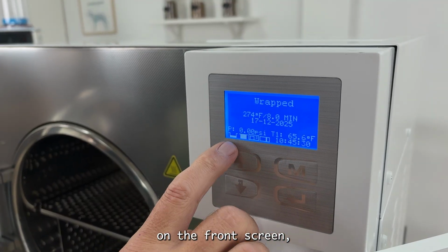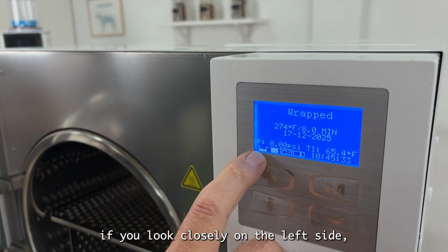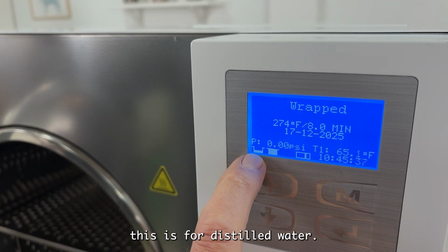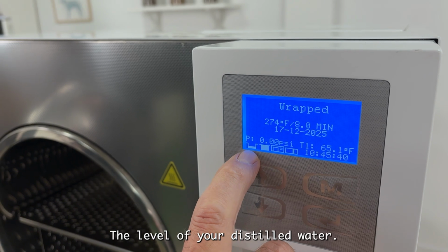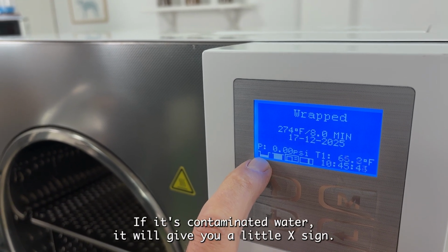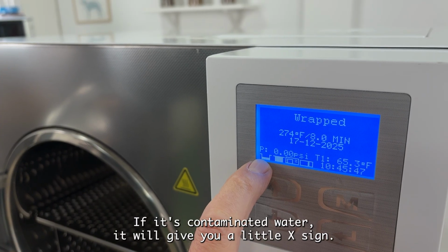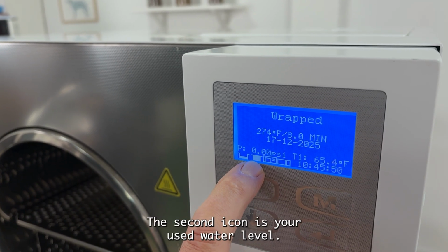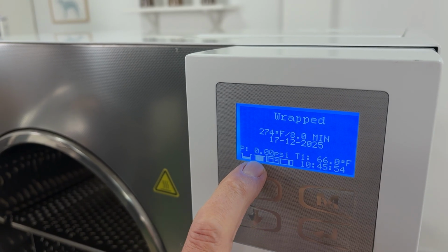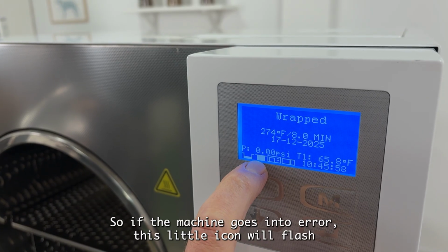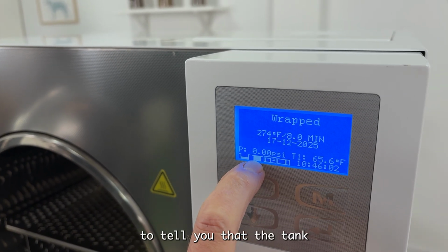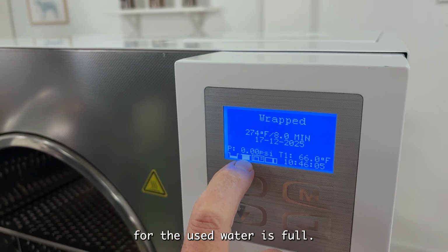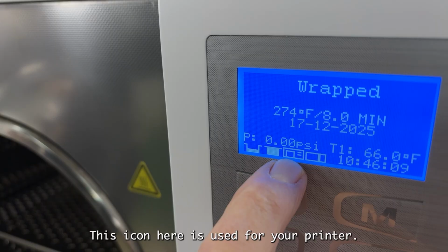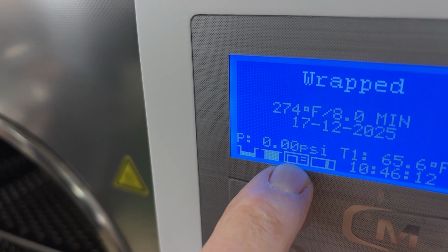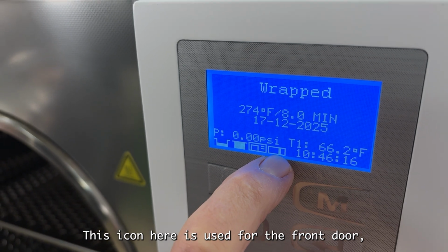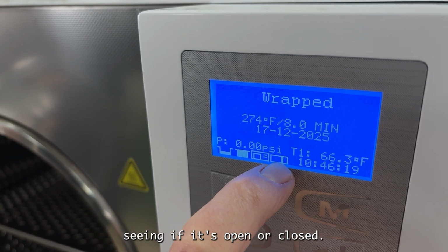On the front screen, if you look closely on the left side, this is for distilled water, the level of your distilled water. Also, it would tell you if your water is not distilled, if it's contaminated water, it will give you a little X sign. The second icon is your used water level. So if the machine goes into error, this little icon will flash to tell you that the tank for the used water is full. This icon here is used for your printer. This icon here is used for the front door, saying if it's open or closed.